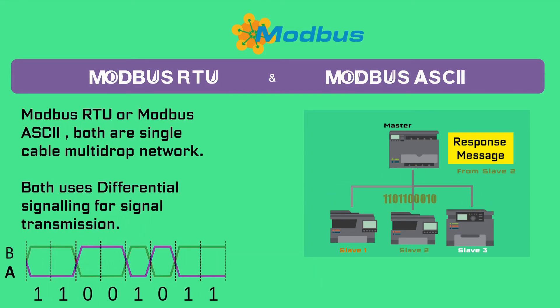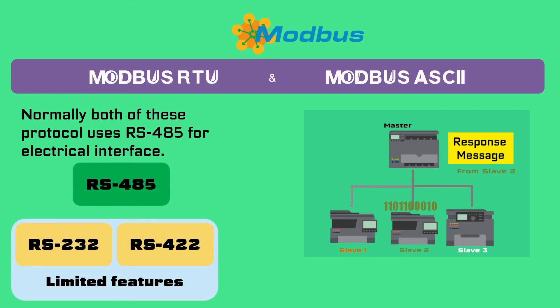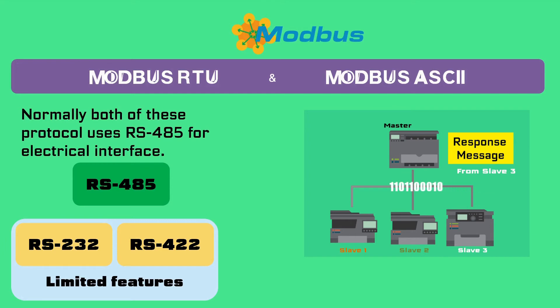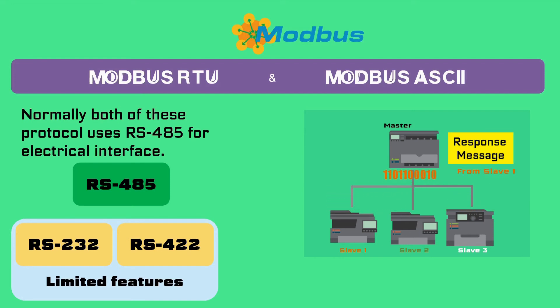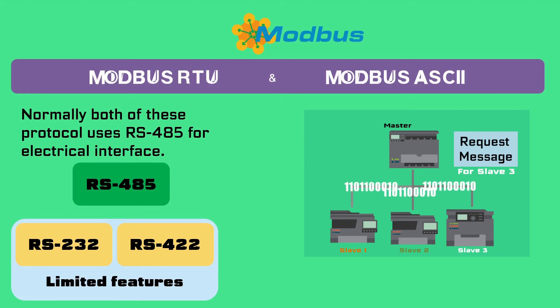It may be noted that both Modbus RTU and Modbus ASCII are RS-485 single-cable multi-drop networks. So when we talk about the message, it is sent in the form of differential signaling, as explained in the session on RS-485. Like RS-485, RS-232 and RS-422 could also be used, but that would limit us in number of nodes, speed, and cable length. Therefore, RS-485 provides the best option among these three for the electrical interface between various Modbus devices.